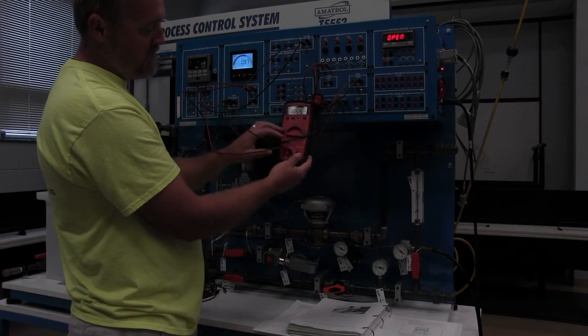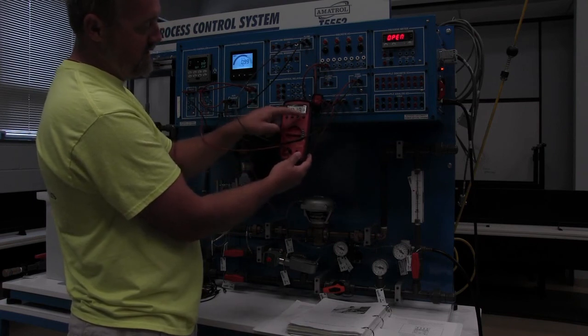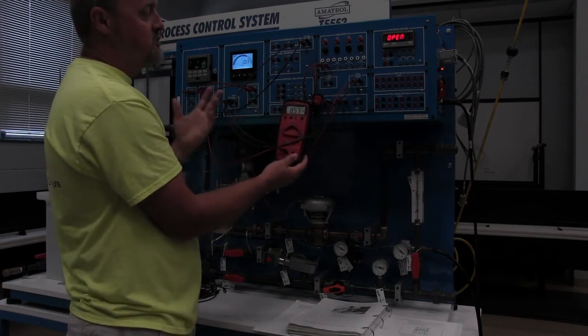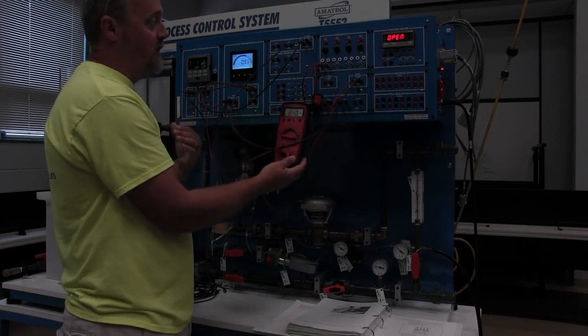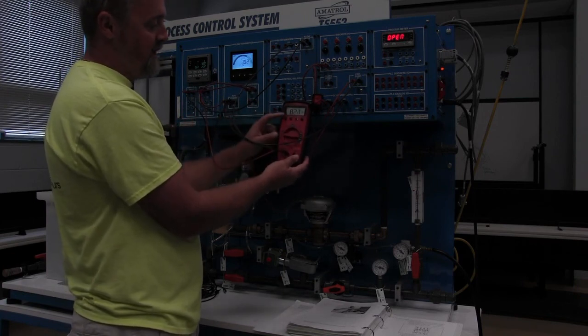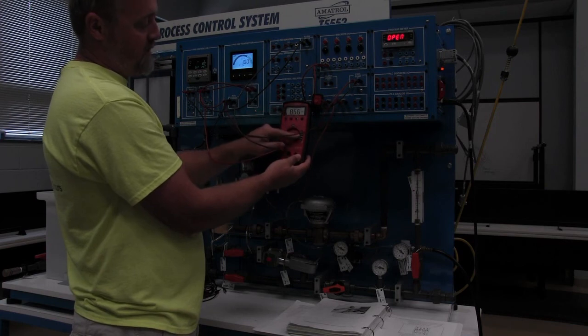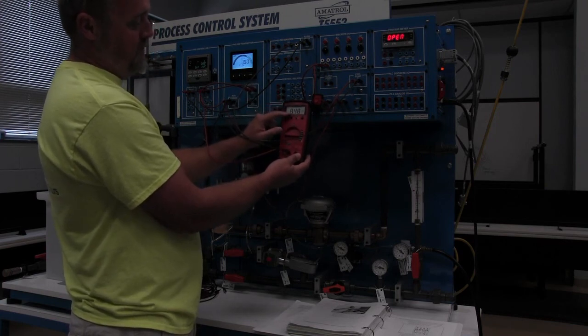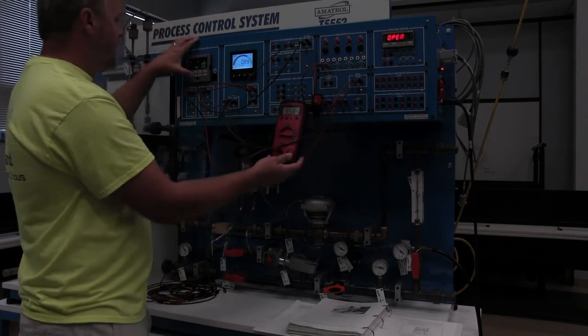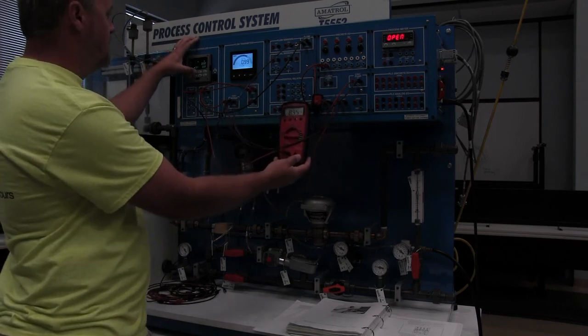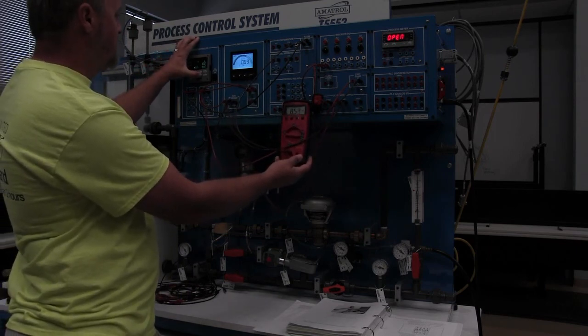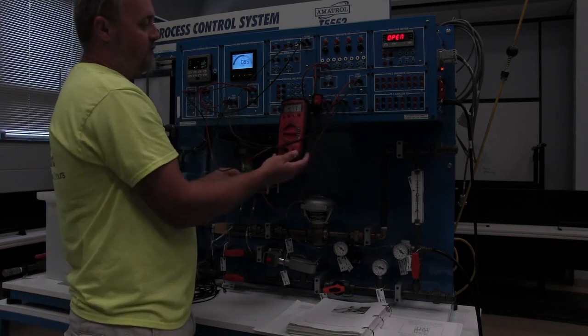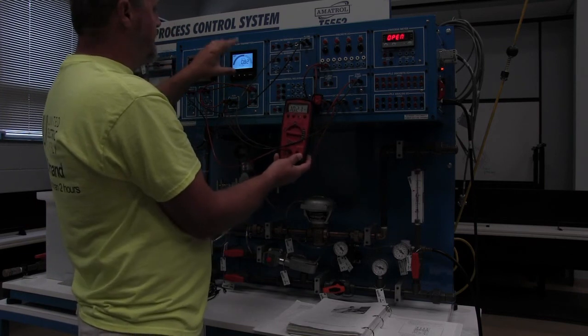It's the milliamps, and we're going to go to DC milliamps, and your max that you should be getting on a 4 to 20 milliamp loop is 20 milliamps. So I set this on 20, and we're reading about an 8.4. If I was to change this set point, I'm going to take this set point down to a 0.4, it's a 0.41.